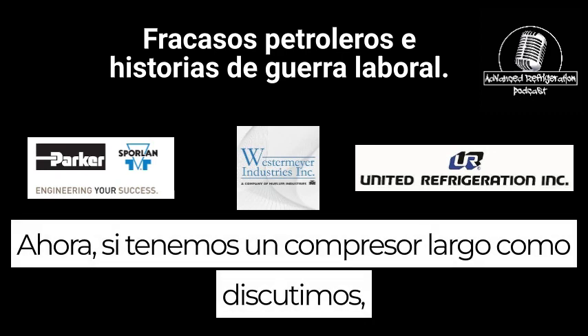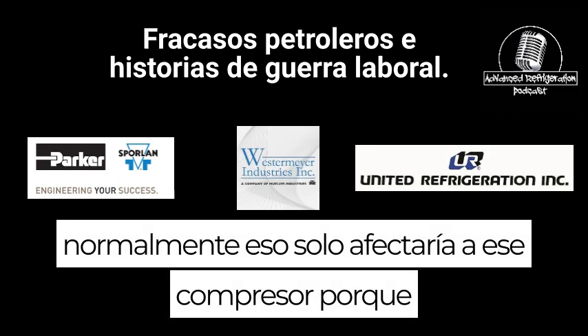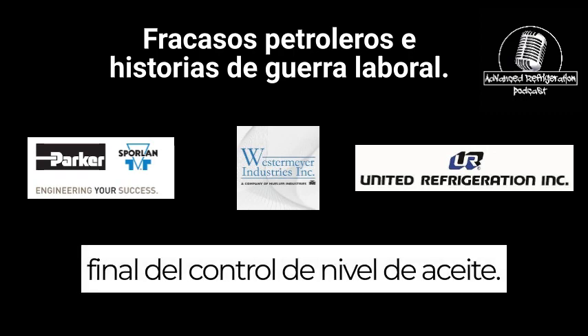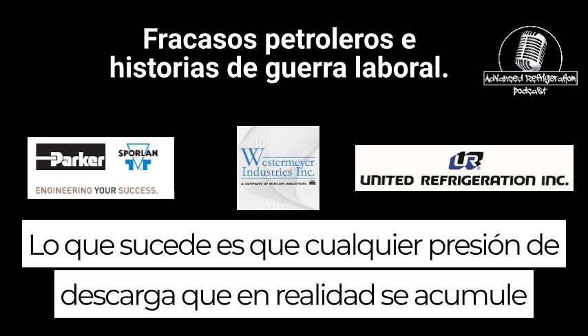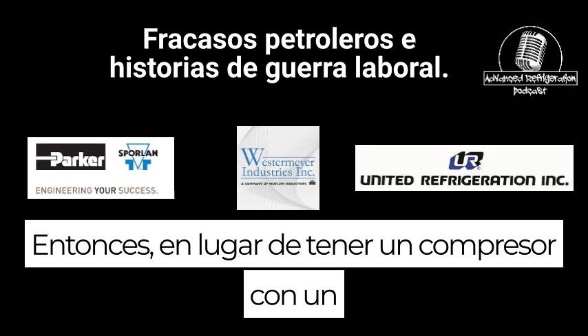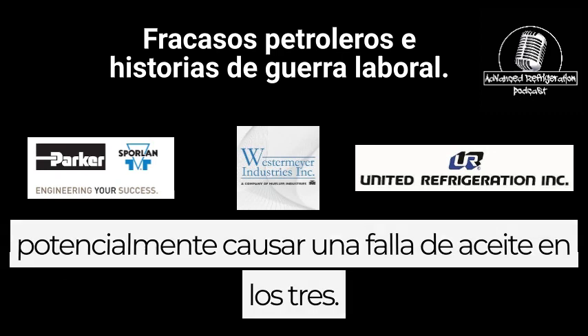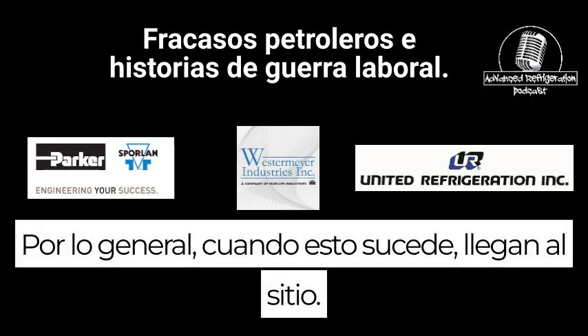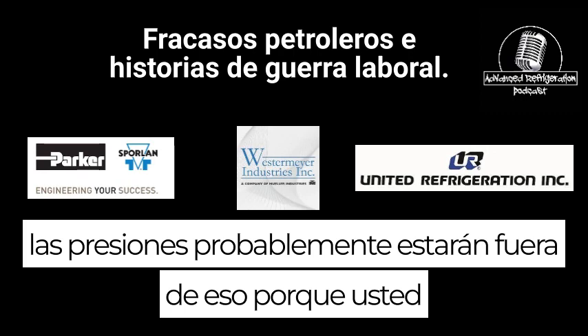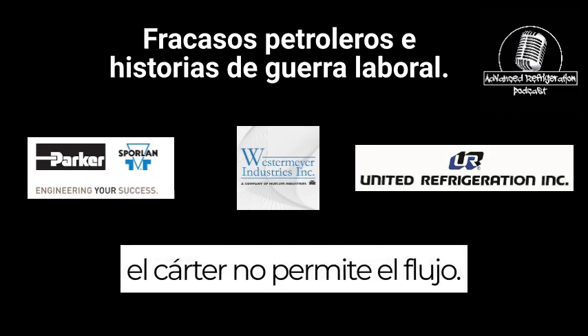Now, if we have one compressor, like we discussed, that's blowing discharge gas into the crankcase, normally that would just affect that one compressor. Because the equalization line is connected to the lower end of the oil level control, any discharge pressure that builds up in that crankcase is going to be shared with the other crankcases. So instead of one compressor having an elevated crankcase pressure, now you have three, which means three compressors that are not going to want to take any of the oil, potentially causing an oil failure on all three. Typically when this happens, you arrive on site and you'll get a failure for oil failures, but you'll also get a failure for high suction, because the compressors will probably be off on that, since too high a discharge pressure going into your crankcase has elevated all the crankcases, not allowing flow.